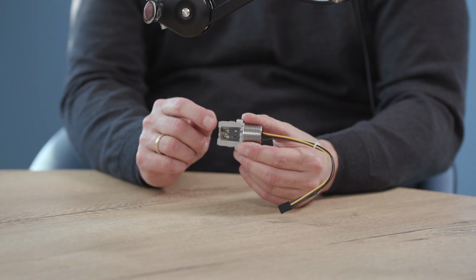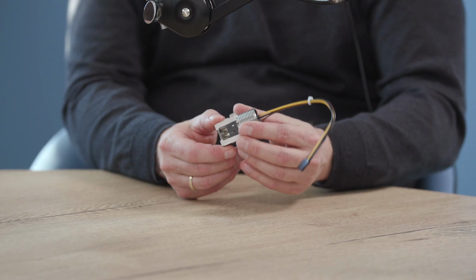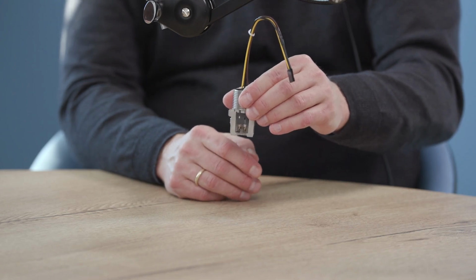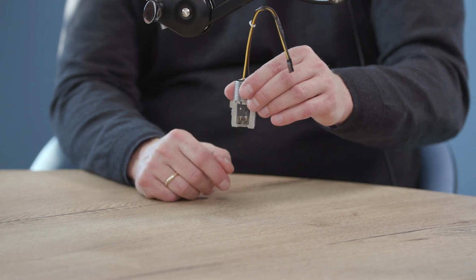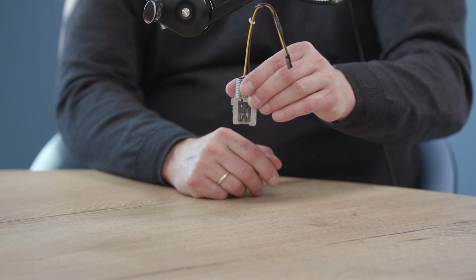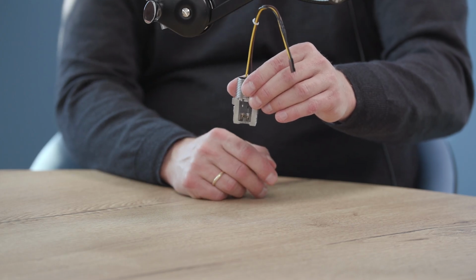So when you're installing, let's look at the considerations when we're installing. Is there anything that stands out particularly for the catalytic bead when locating a device? I would say, yes, when we compare to infrared technology, for example, in a lot of cases sensors should be oriented so that the opening is facing downwards. This protects the opening from dirt, dust, also in winter time from snow, or if you have heavy rain, so that water drops are not blocking the gas entry. So this is more particular, I would say, to catalytic bead, but also to some others.